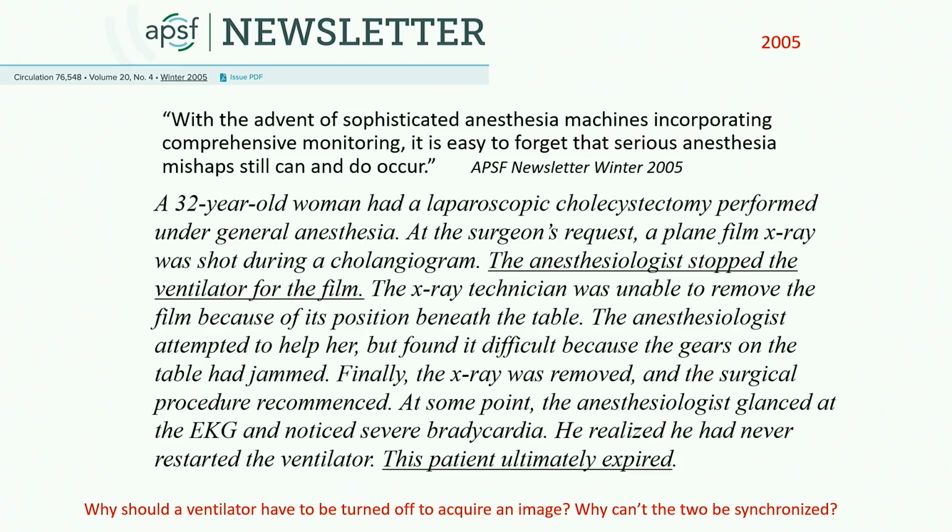Now, this is something from 2005. The Anesthesia Patient Safety Foundation, in their winter newsletter and their workshop, talked about the unfortunate death of a 32-year-old patient having a laparoscopic cholecystectomy. They turned off the ventilator, left the room to get the x-ray, and then forgot to turn it back on in a timely period because they were preoccupied with a problem with the x-ray cassette.